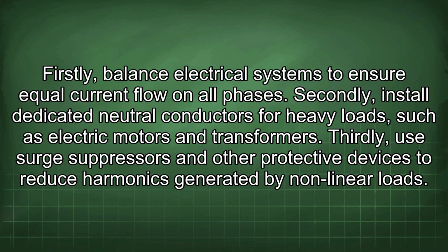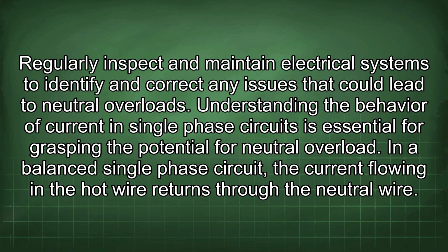Firstly, balance electrical systems to ensure equal current flow on all phases. Secondly, install dedicated neutral conductors for heavy loads such as electric motors and transformers. Thirdly, use surge suppressors and other protective devices to reduce harmonics generated by nonlinear loads. Regularly inspect and maintain electrical systems to identify and correct any issues that could lead to neutral overloads.